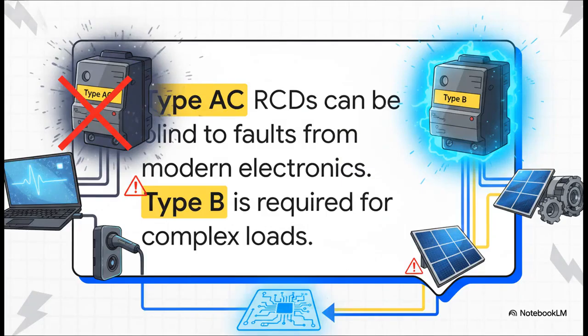So, the takeaway here is huge. Picking the wrong type of RCD isn't some small mistake. It's a massive safety failure. As the standards like AS/NZS 3000 keep evolving, the message is loud and clear. You can't just slap a Type AC RCD on a circuit that has modern electronics anymore. It's just not acceptable. Type A is really the new minimum, and for the heavy hitters like VSDs or PV systems, you're often required to use a Type B.